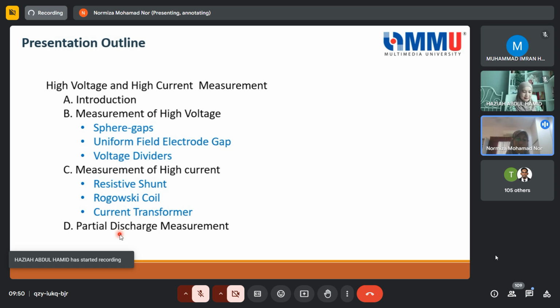Because this partial discharge measurement is not only conducted in the lab, but also at field sites. And other than offline measurement at site, it can also be monitored online nowadays with the digital substation and digital technologies. So we are able to observe it online as well. We will look into this because for any equipment, we want to see the health of the equipment online as well as offline. So we will cover this part as well, which is part D here.